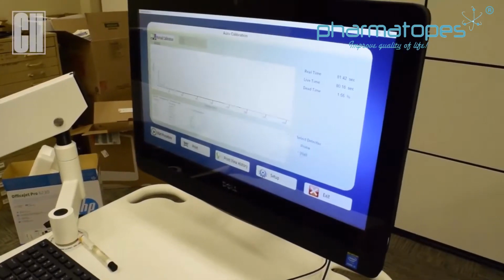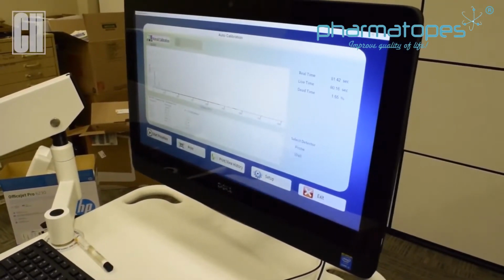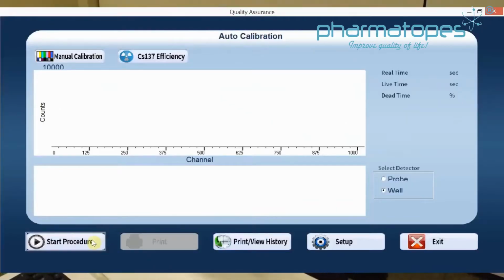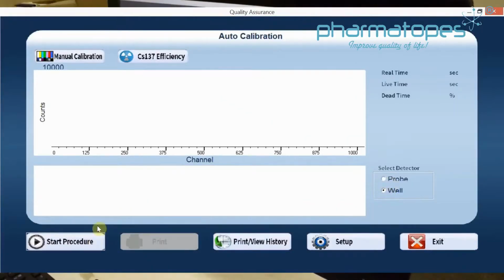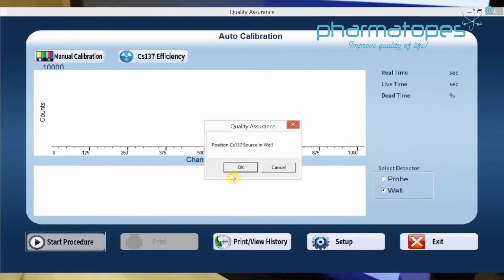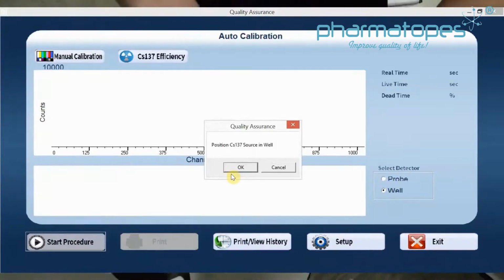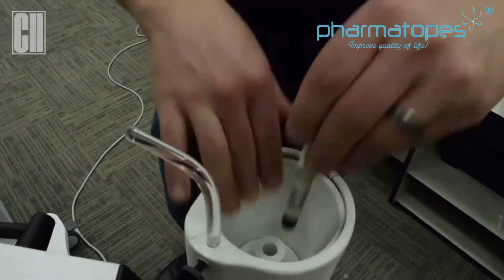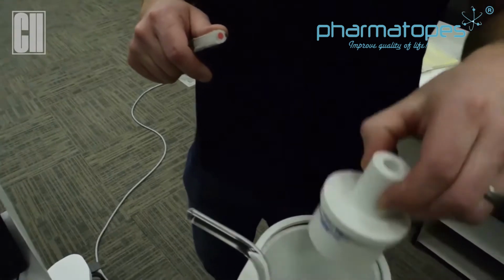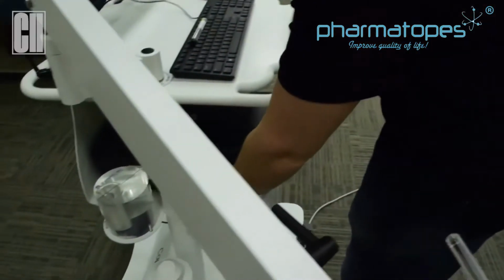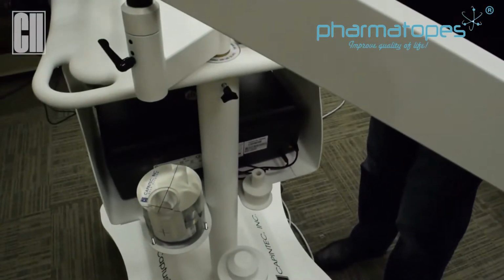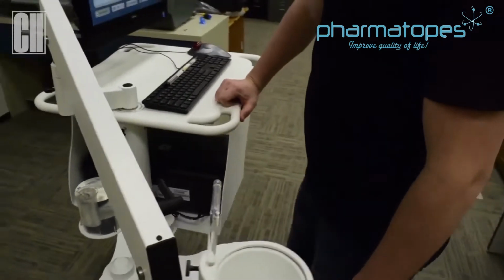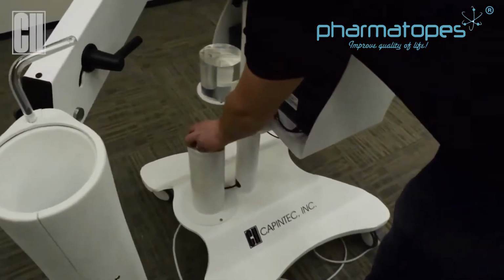And run calibration on the well. So when we do start procedure, it's going to tell us position cesium in the well detector now. At this time, we can remove our europium source that was in our probe, and then also our source holder, and put a new holder for the time being. And now that we're calibrating the well counter, we're going to take off the top lid.